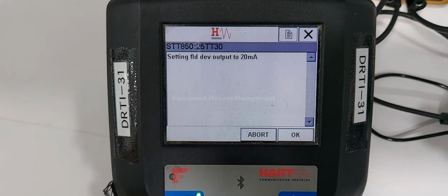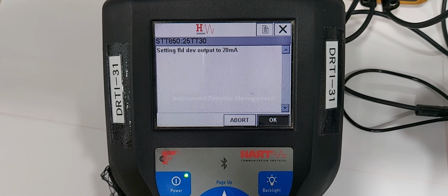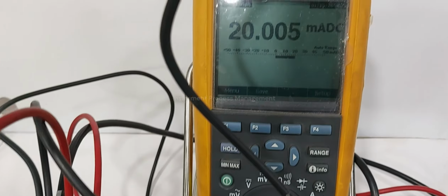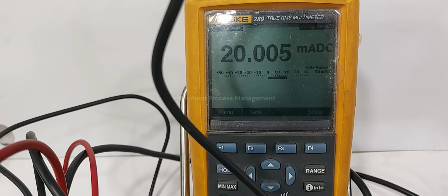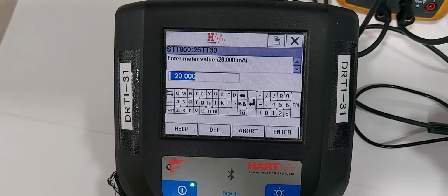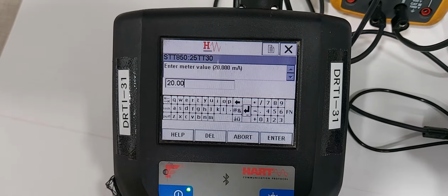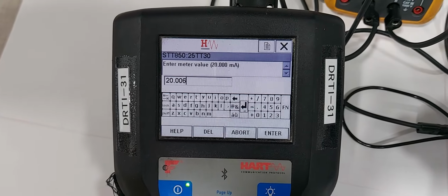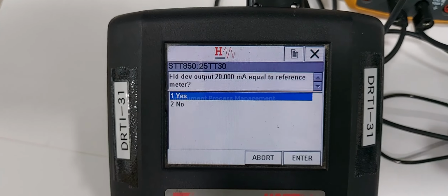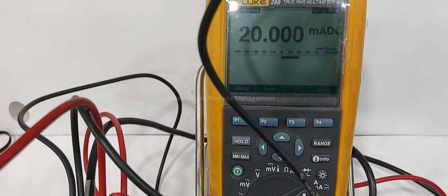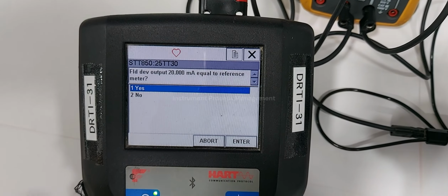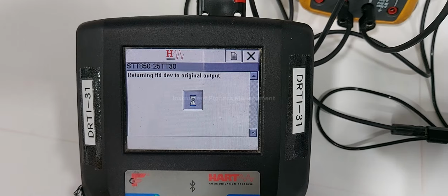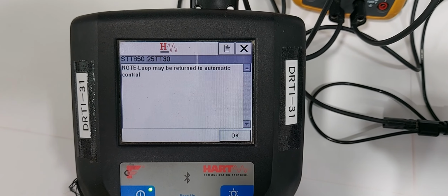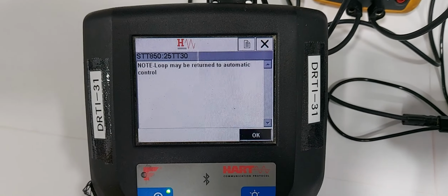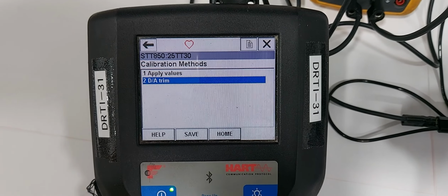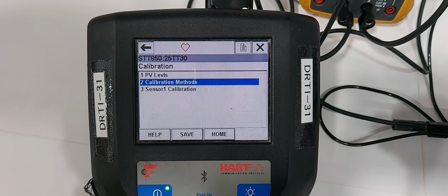Next set the field device output to 20 milliamps, then OK. Now the reference multimeter is showing 20.005 milliamps. The same value we are entering in the communicator, 20.005, then enter. Now the output value equals the reference value. Both are the same. Then press enter, then press OK. Back to menu. This is the DA trim calibration procedure.